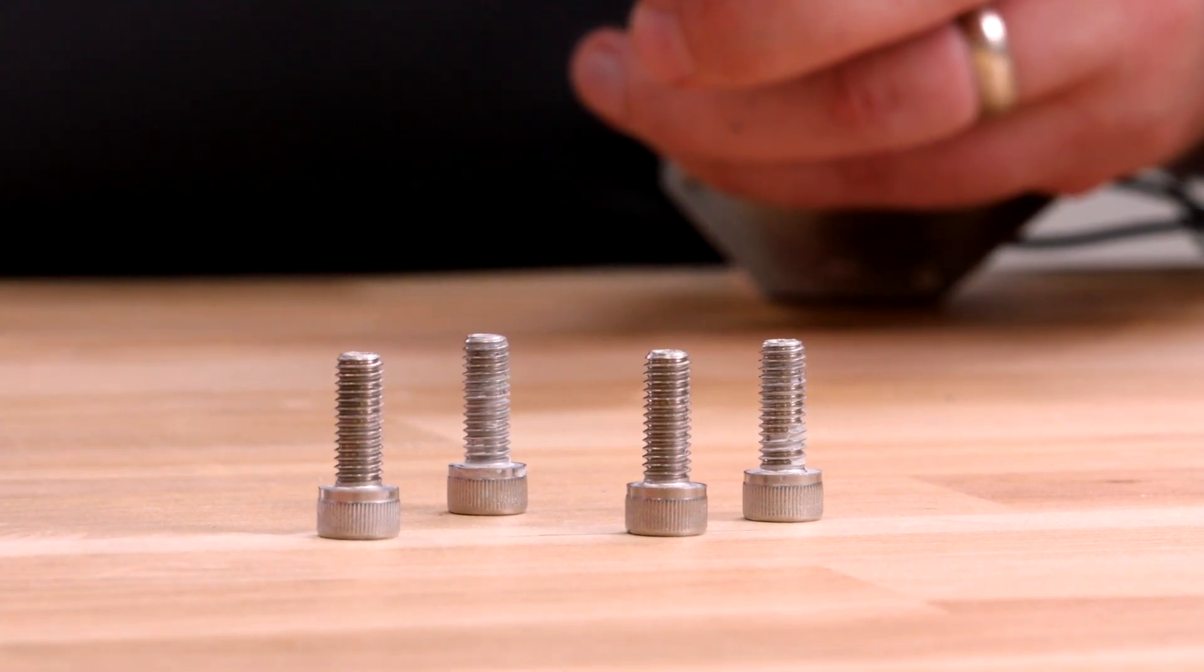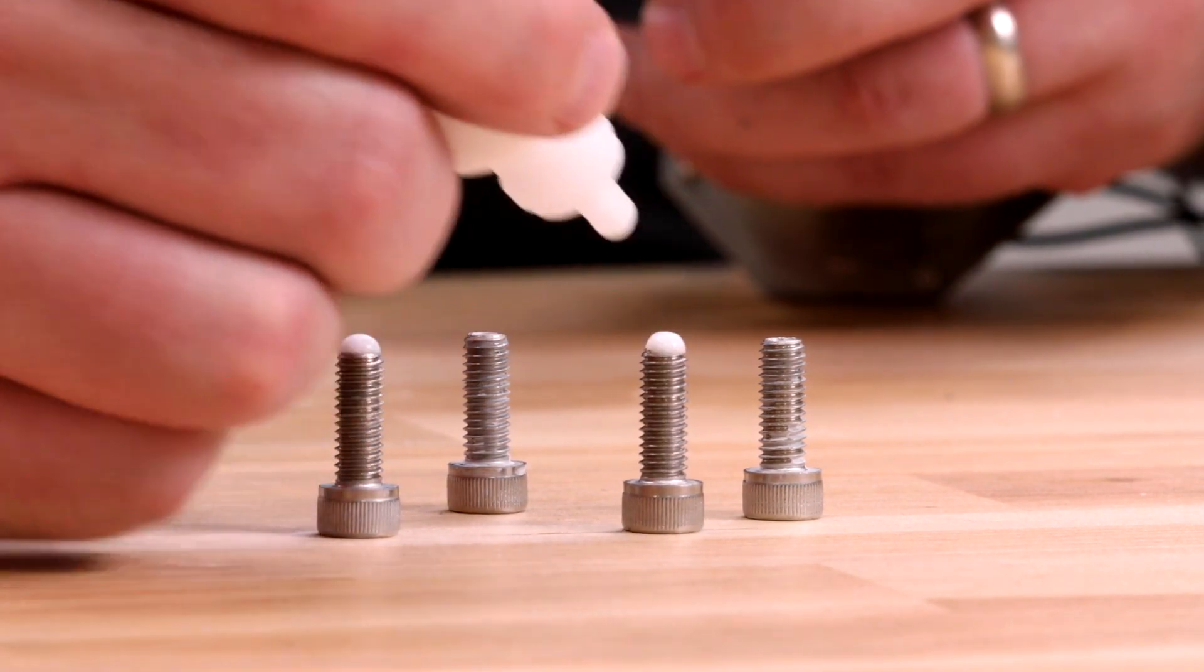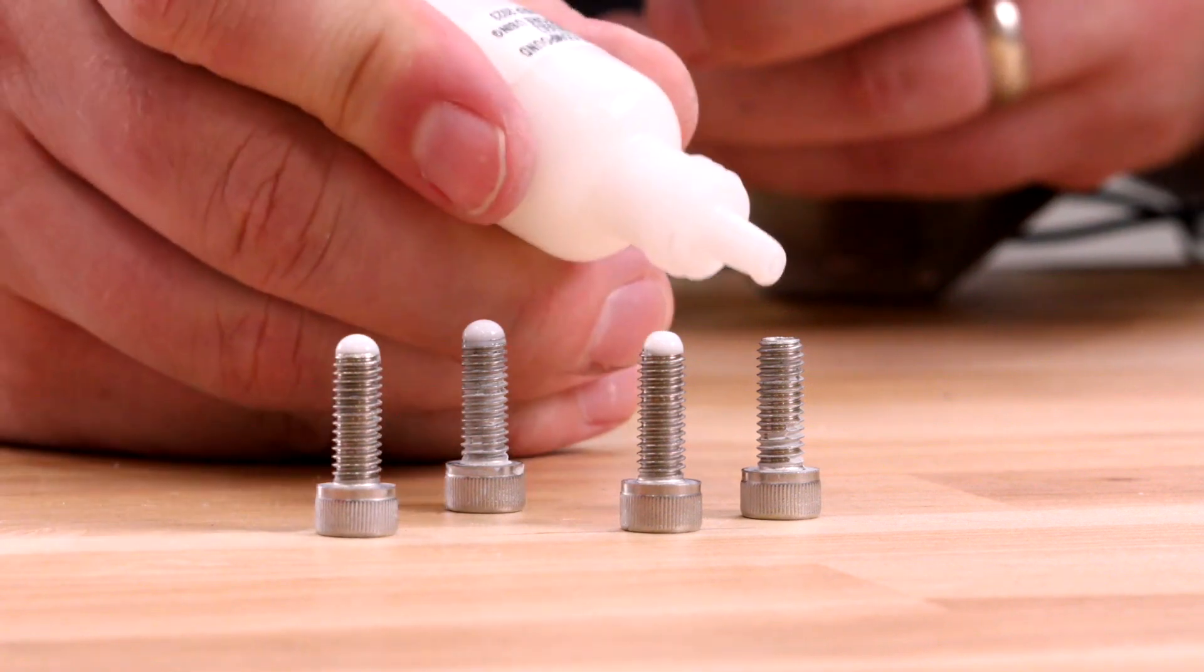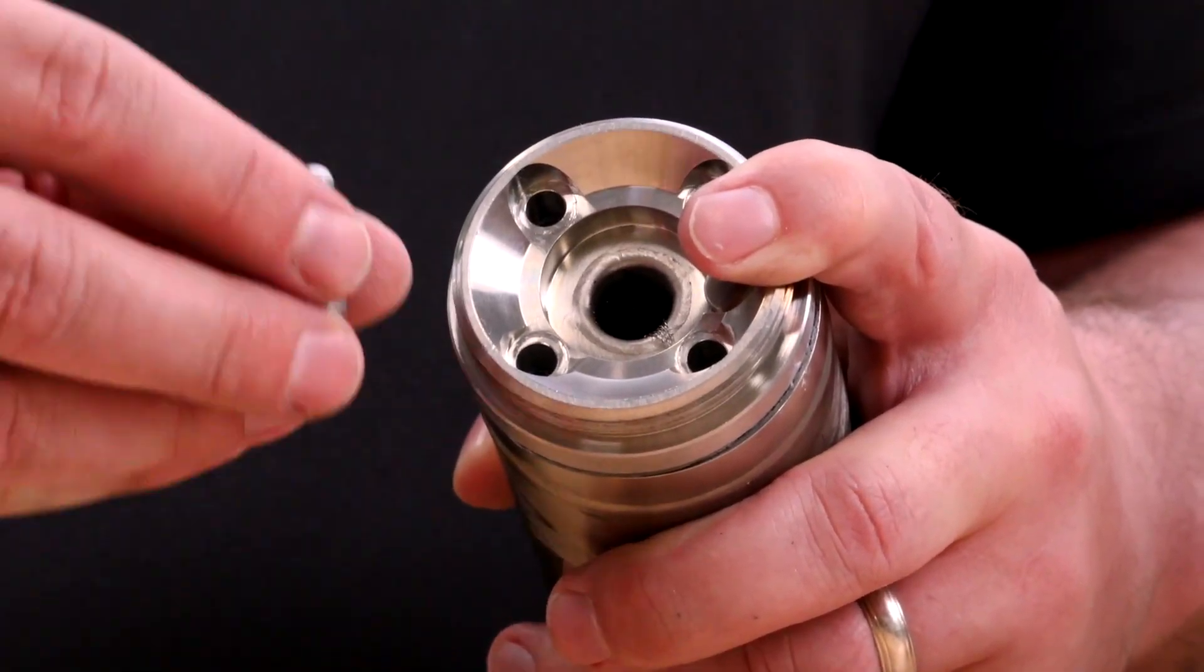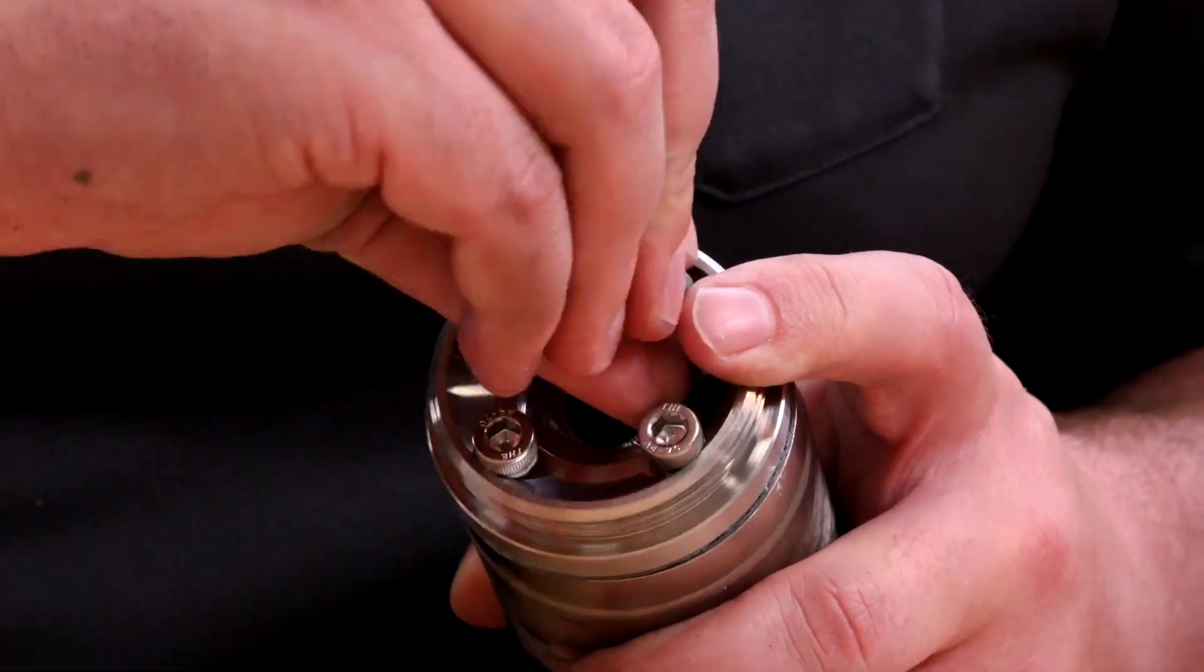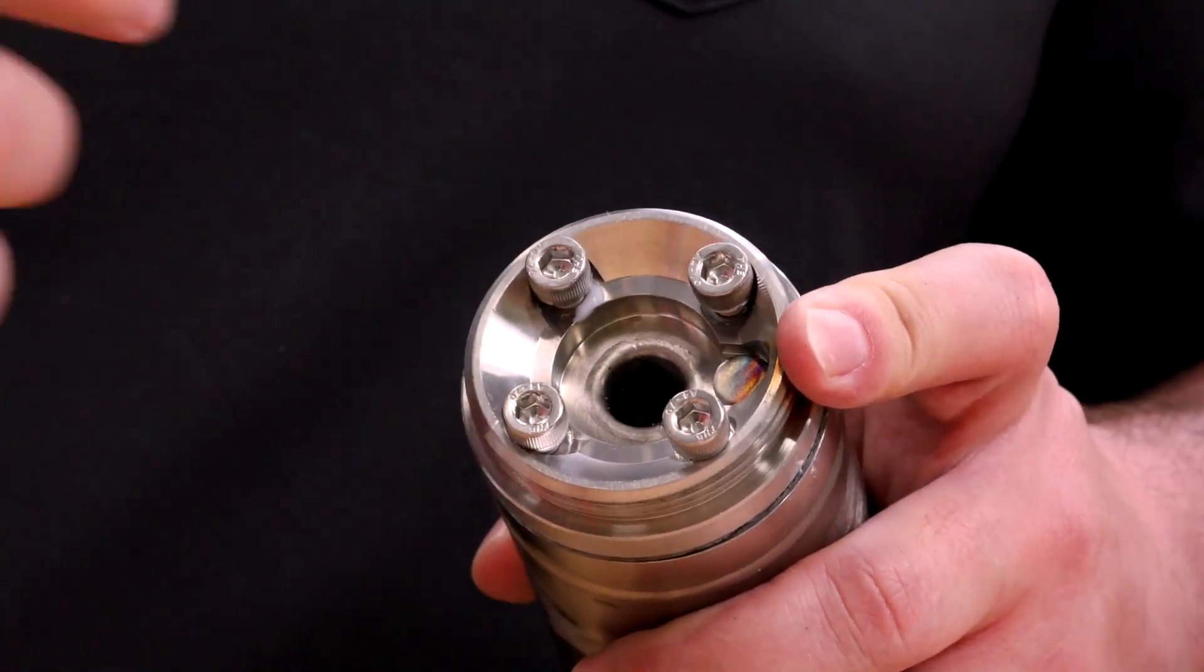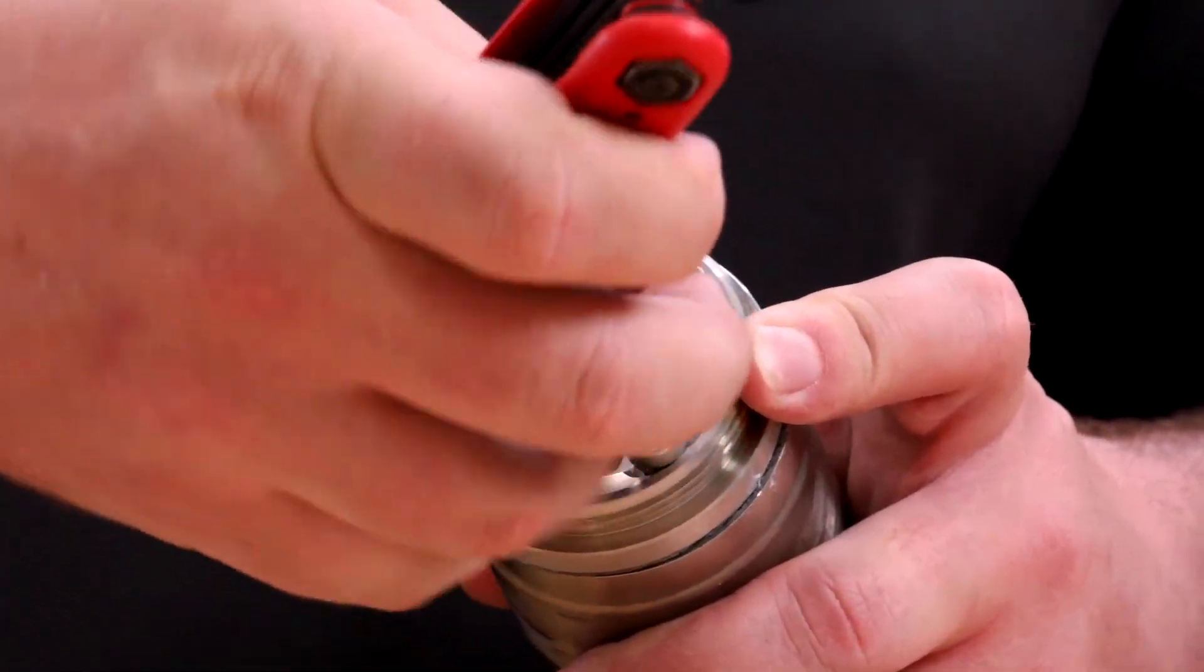Apply a small amount of anti-seize compound to the screw threads. Use the screws to secure the new O2 cell to the heater tube. Torque the screws to 35 inch-pounds.